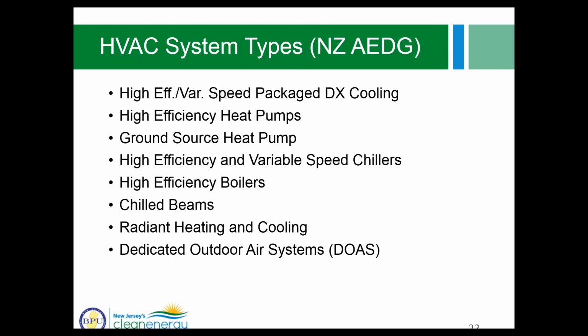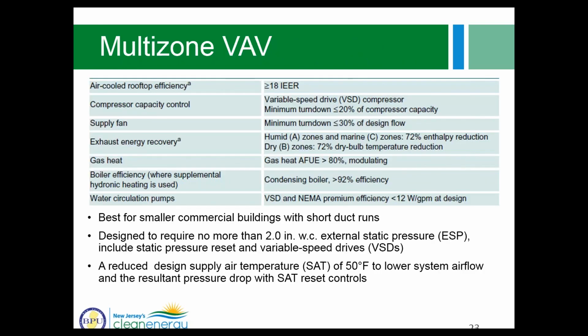So next, I'll talk about opportunities related to HVAC, and there, on a high level, opportunities involve using more efficient HVAC system type, such as, for example, radiant heating and cooling, VRF, heat pumps, ground source heat pumps, using designs that include dedicated outdoor air systems, or alternatively or additionally, opportunities involve specifying systems with higher efficiency, for example, high performance boilers, high performance chillers. So here are a few examples of high performance systems based on ASHRAE Advanced Energy Design Guide.